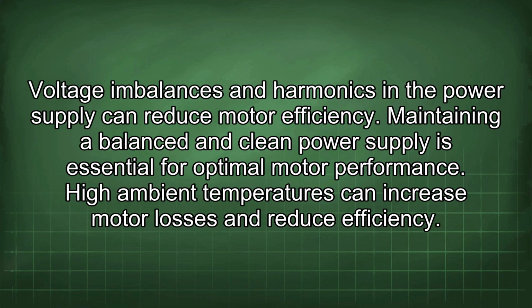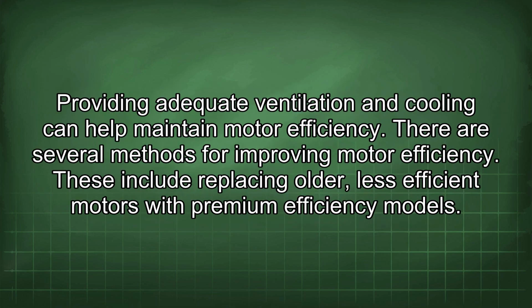Voltage imbalances and harmonics in the power supply can reduce motor efficiency. Maintaining a balanced and clean power supply is essential for optimal motor performance. High ambient temperatures can increase motor losses and reduce efficiency. Providing adequate ventilation and cooling can help maintain motor efficiency.